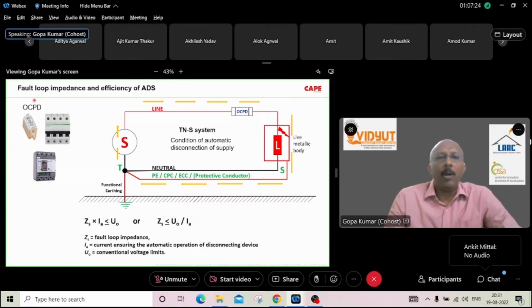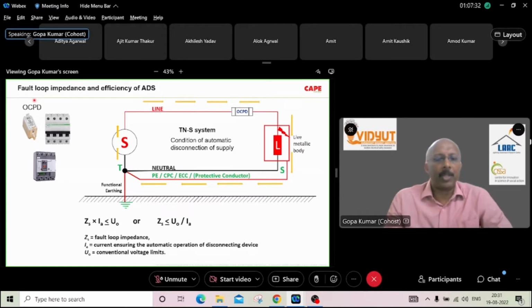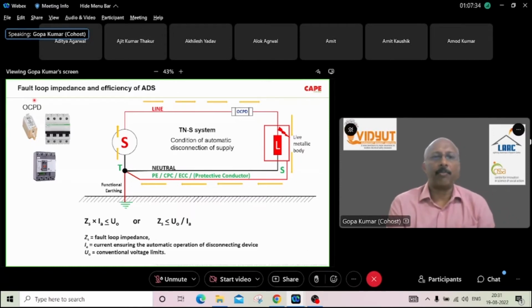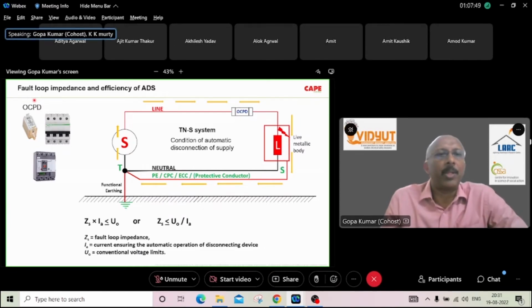Now, all electrical engineers follow 1 standard for earthing, IS 3043. And if you look at the tenders of government buildings, they always say earthing as per IS 3043, plate earthing, pipe earthing, and all these things. But please understand that IS 3043 is not explaining about plate and pipe. IS 3043 is explaining how to reduce the fault loop impedance in your network and how to make your MCB efficient to trip during a faulty condition.